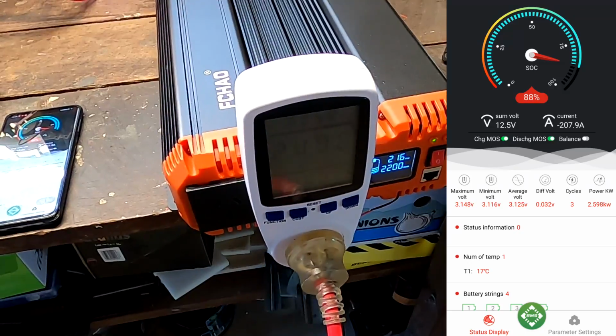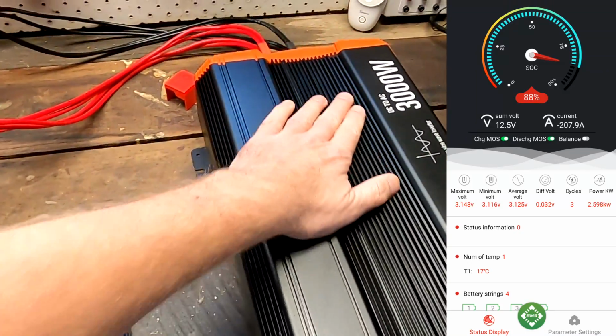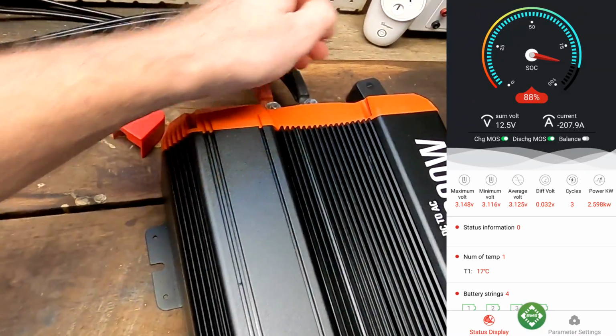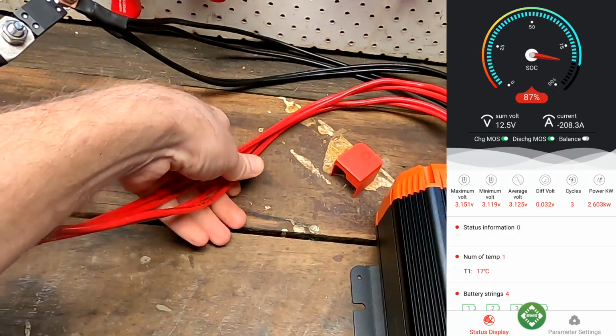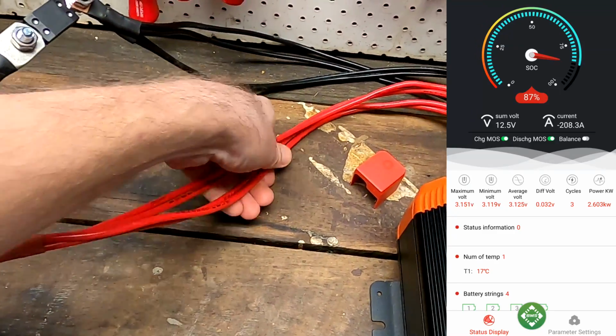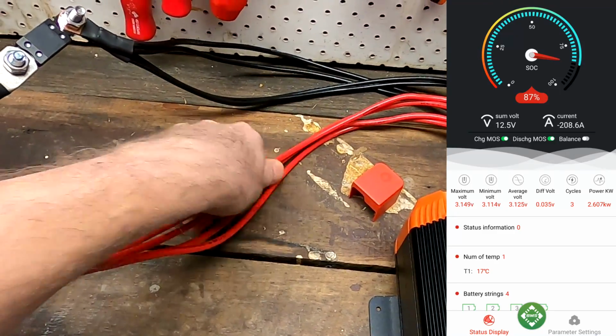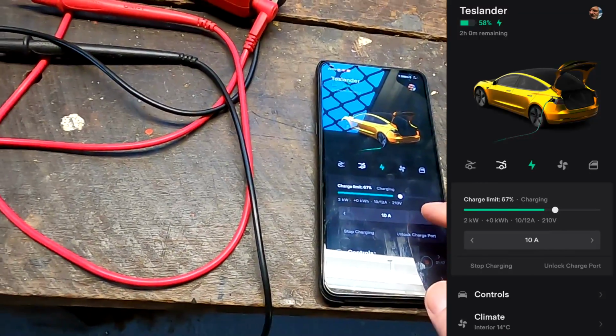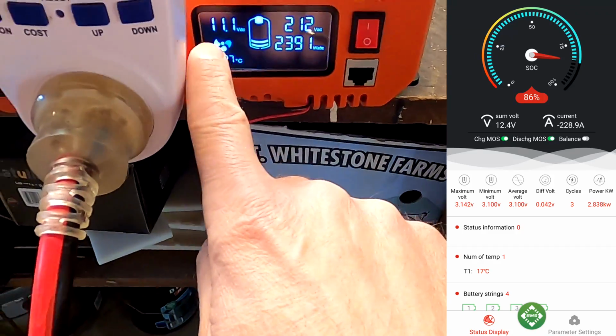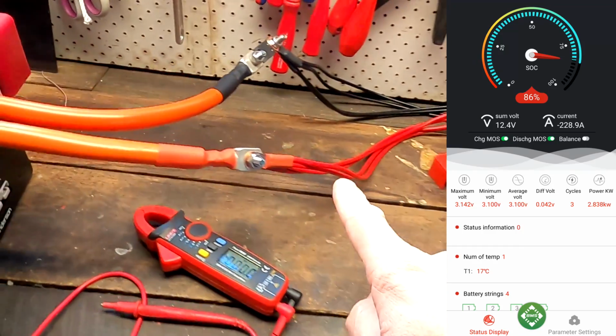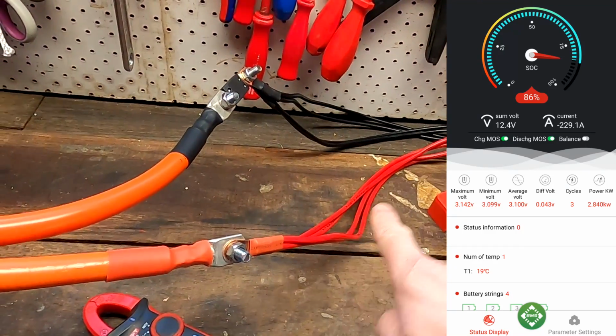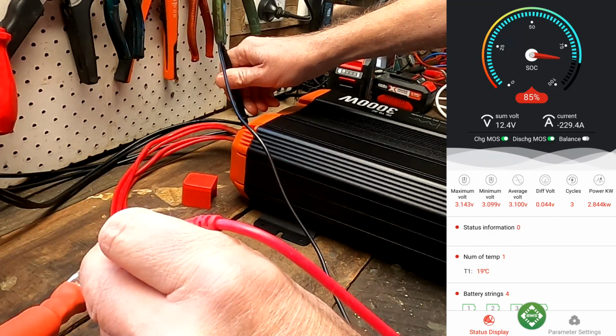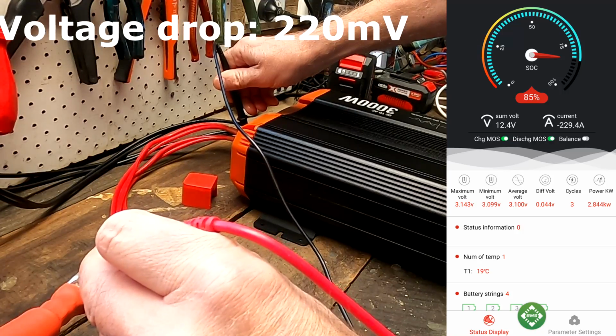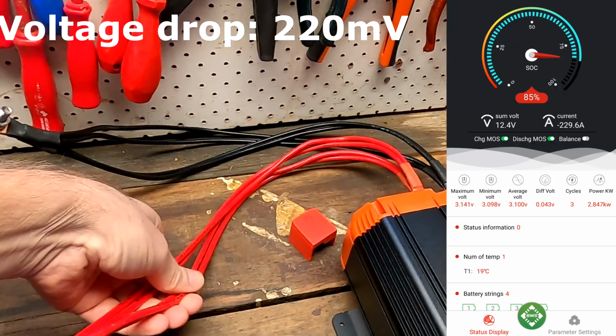2.2 kilowatts we are pulling from the inverter. Nothing gets warm, both fans are on, but these cables here are my main concern, because they are nice and warm already. Okay, let's go to 11. I think we will have a low voltage disconnect at some stage here, because we are losing so much power across these wires now.